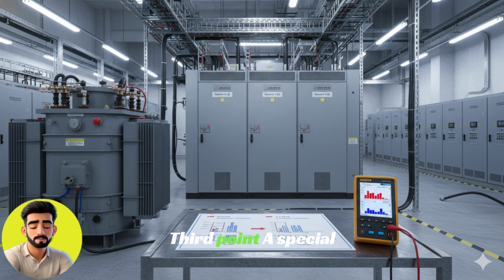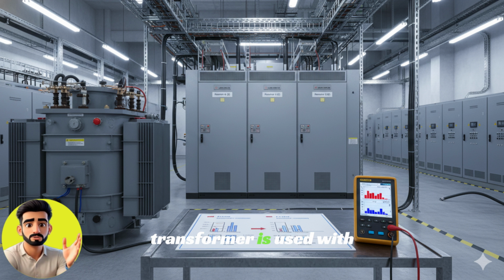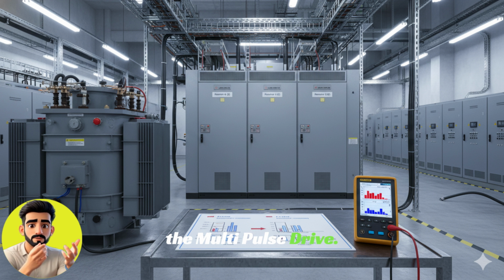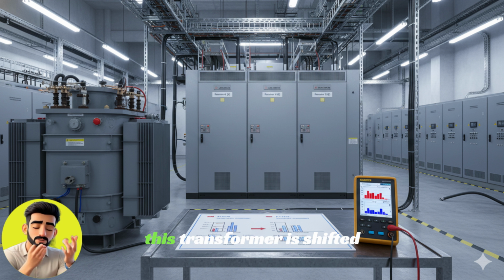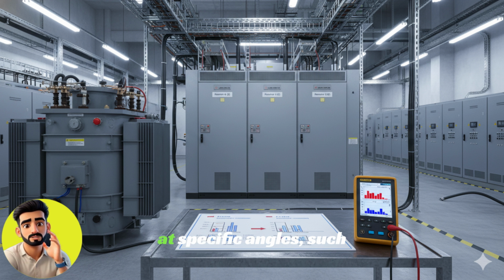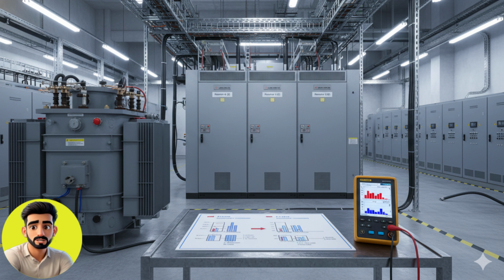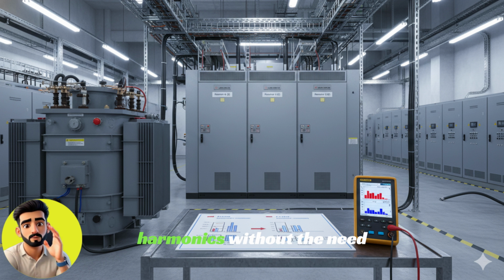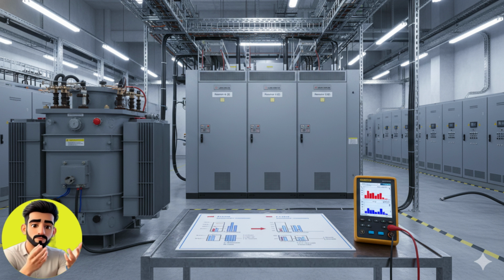Third point. A special transformer is used with the multi-pulse drive. It is called a phase-shifting transformer. The secondary winding of this transformer is shifted at specific angles, such as 30 degrees or 20 degrees. This shift naturally cancels harmonics without the need for any extra filters.